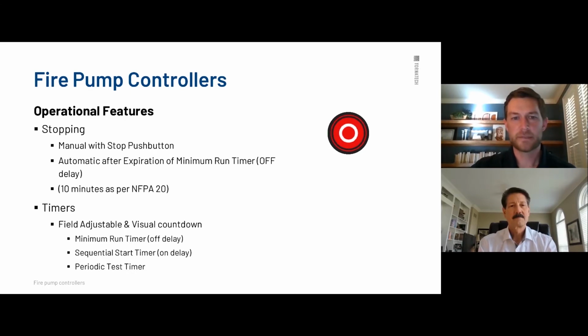Some of the other timers that we have are the minimum run, like an off delay, or an on delay for a sequential start timer. If you have multiple pumps running in parallel, then you can have one start, say 15 seconds after the other one, and it's only going to start if the conditions aren't satisfied and so on. However many you have, if it's going to be a sequential start like that, you can just delay each start time. And then the periodic test timer, that's going to be based on that push button. The test where for the diesel, you've got to run it for 30 minutes every week, and for the electric it's every month for 10. That's the periodic test timer. Those are adjustable.